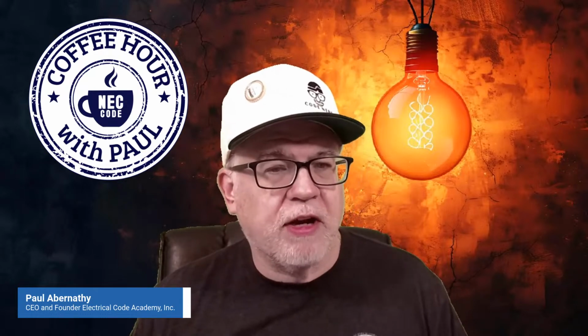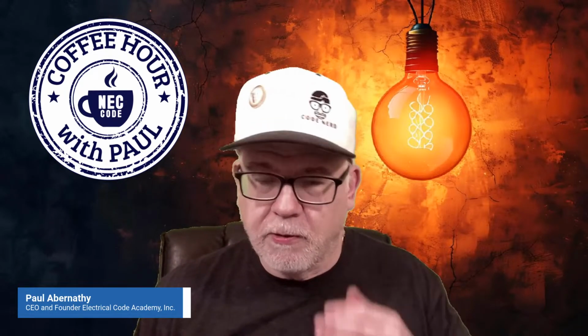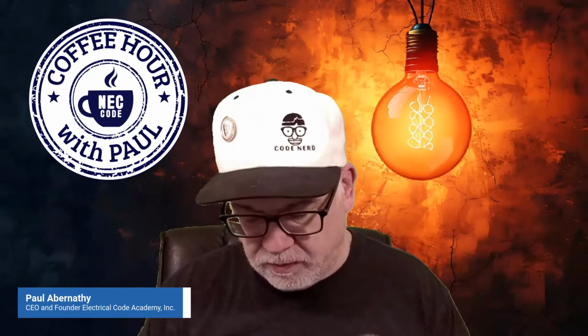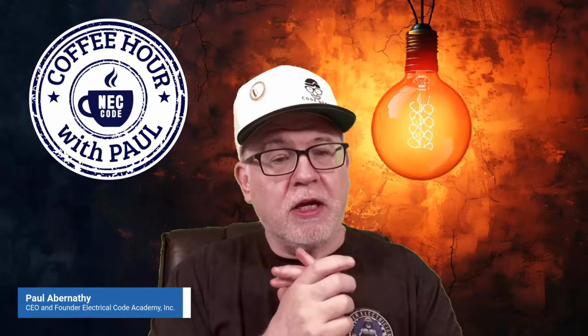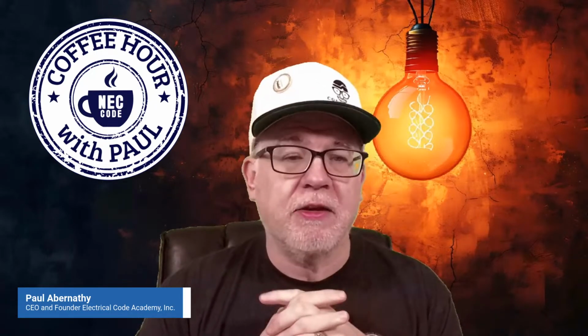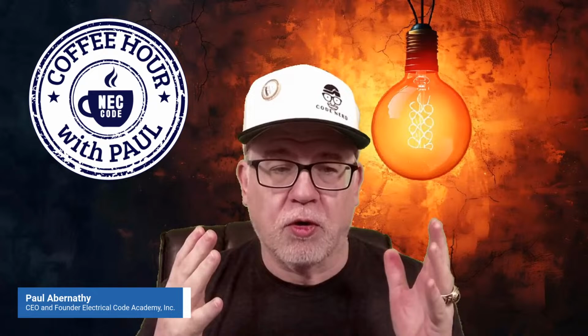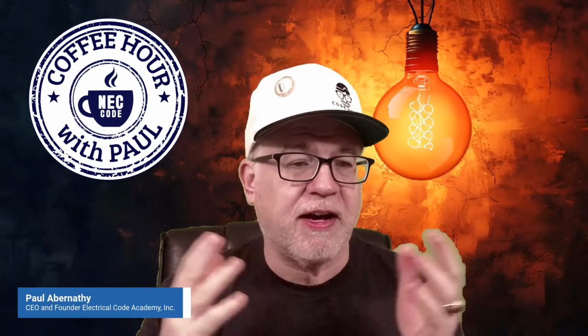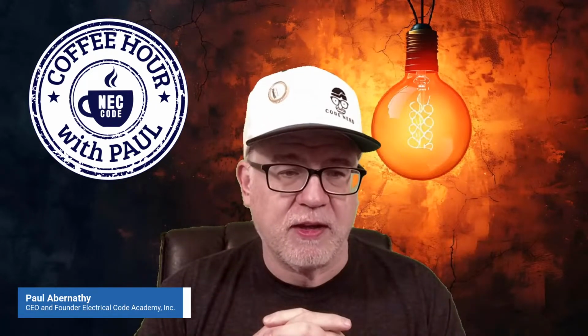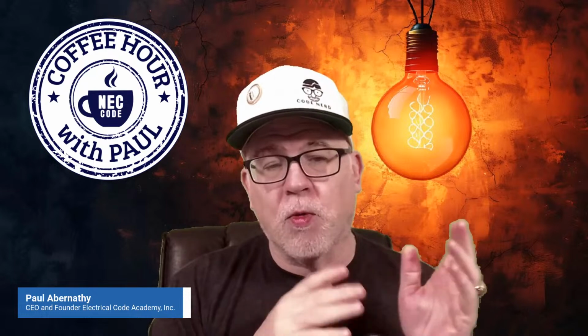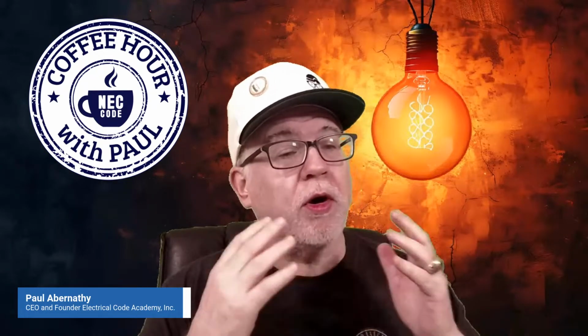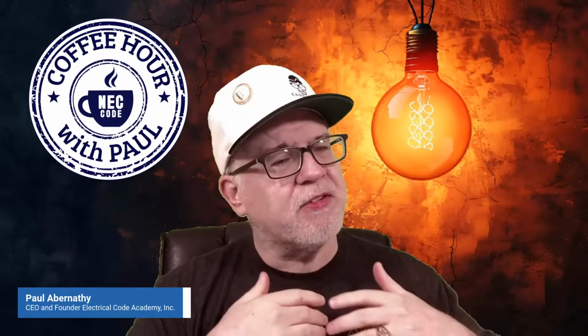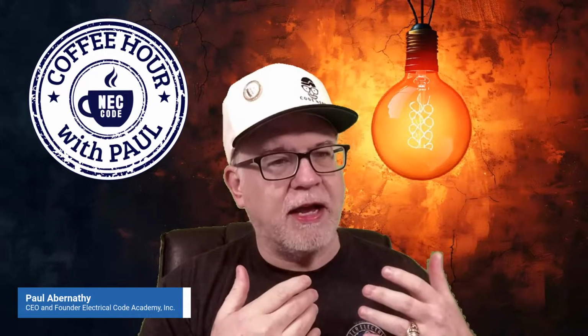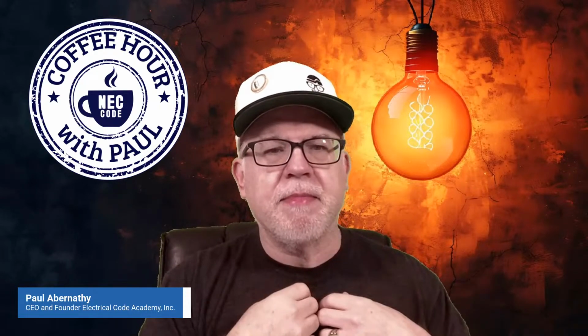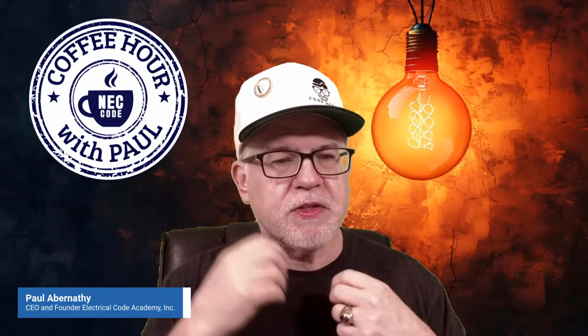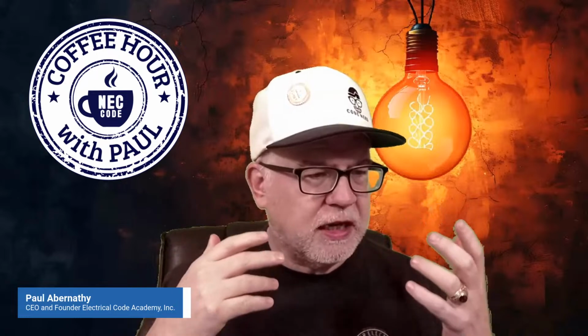All right, so we're going to talk transformers today. All right, so primary protection. Okay, for those that aren't, I'll set the stage. What we're talking about is a typical transformer. Let's say we're going to stick with the 75 kVA transformer for simplicity's sake. It's going to be a 480 primary, and we're only working on the primary. But I'll make some comments that are educational for you that maybe will help check some of those boxes.